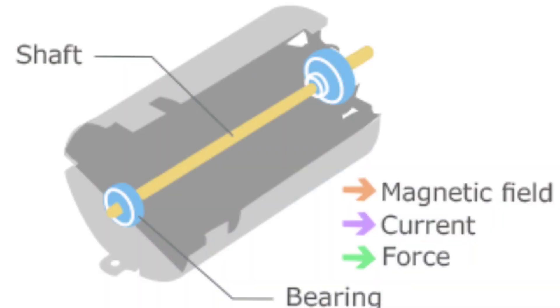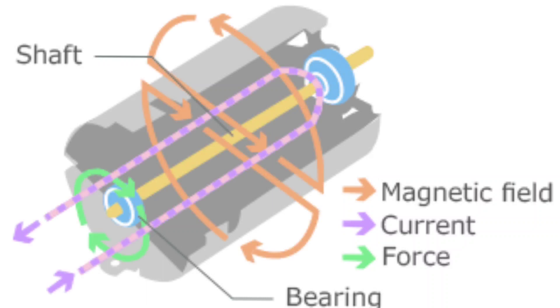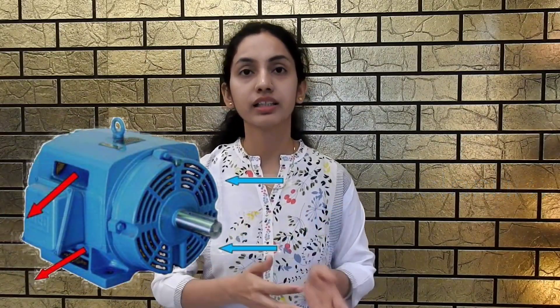Then the motor shaft. The rotor is pressed onto a steel shaft to form a rotor assembly. The shaft extends outside the motor casing, allowing connection to an external system to transmit rotational power. Bearings hold the motor shaft in place and minimize shaft friction with the casing, which increases the motor's efficiency. The enclosure protects the internal parts of the motor from water and other environmental elements, and consists of a frame and two end brackets.